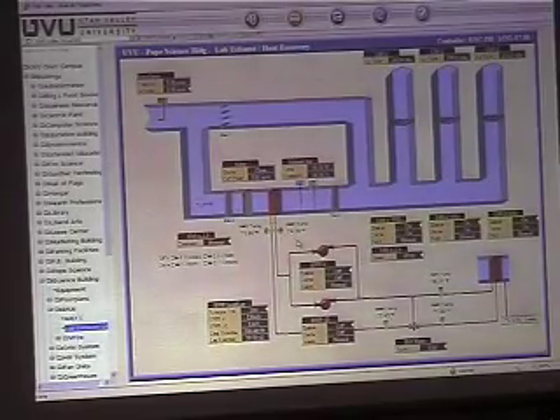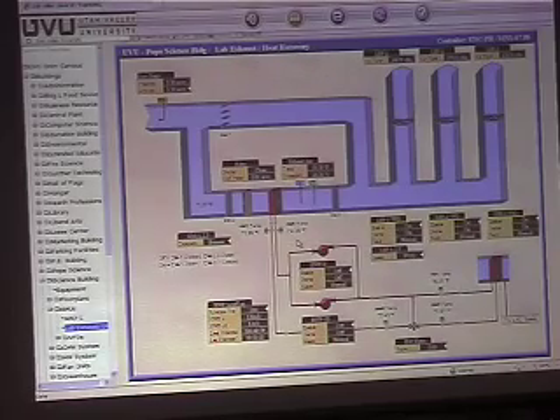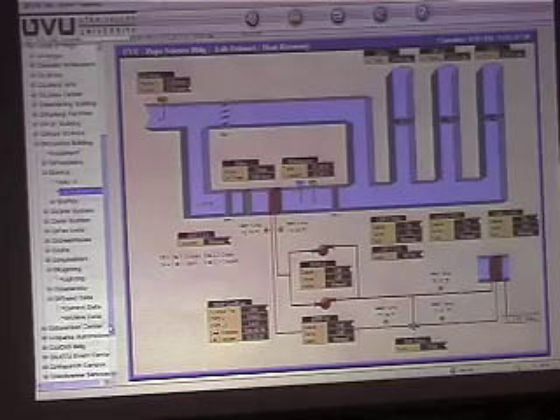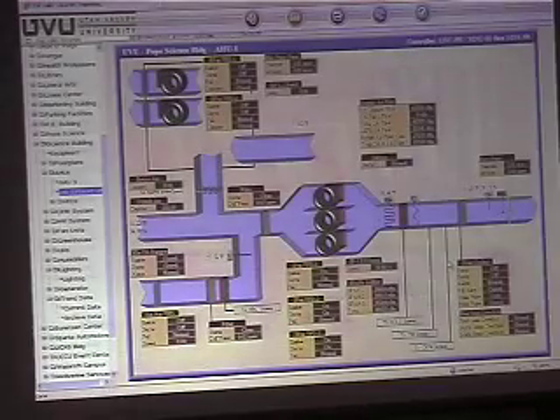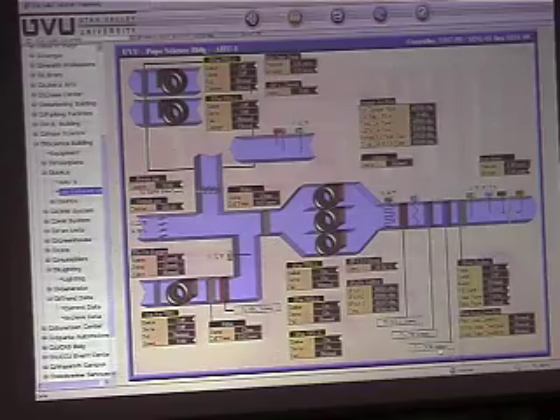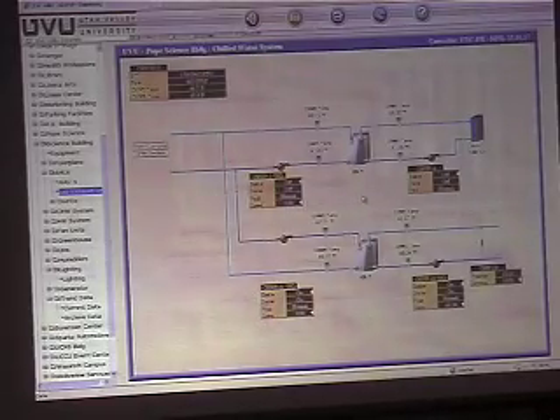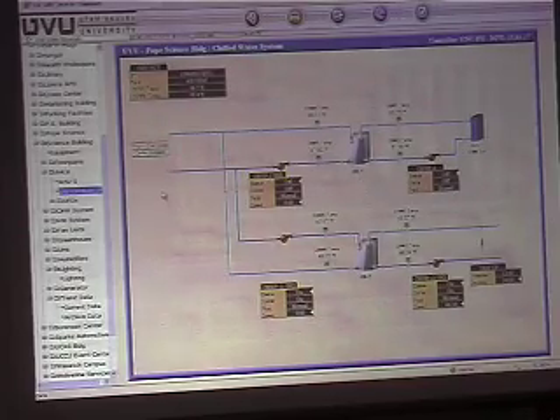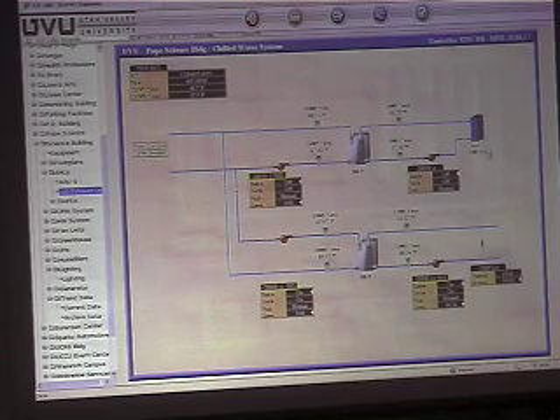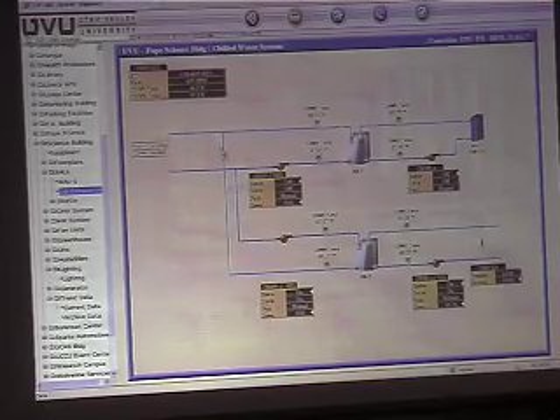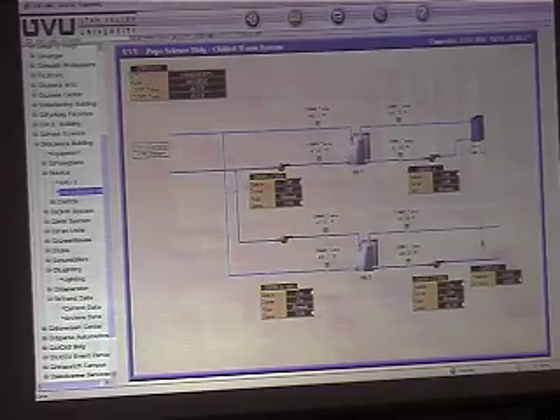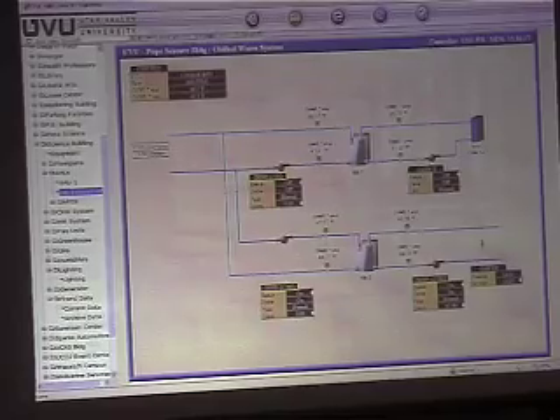Any questions on the lab exhaust fan? Then you've got the chilled water coil here. So that screen here. There are two heat exchangers off of your chilled water coming from the campus. One serves that coil in the air handler. It's got a pump that draws water off of the loop, circulates through that heat exchanger and back out to the campus line. And then there's another one on the glycol loop here for the chilled water coil.